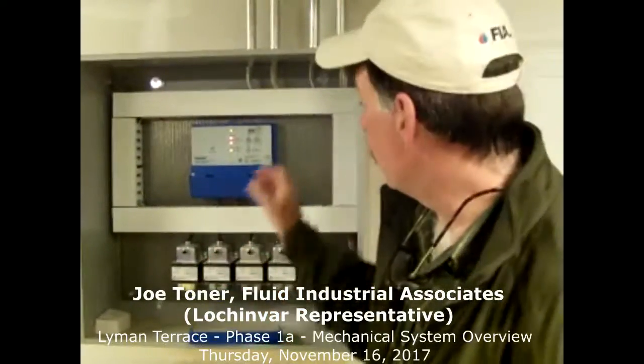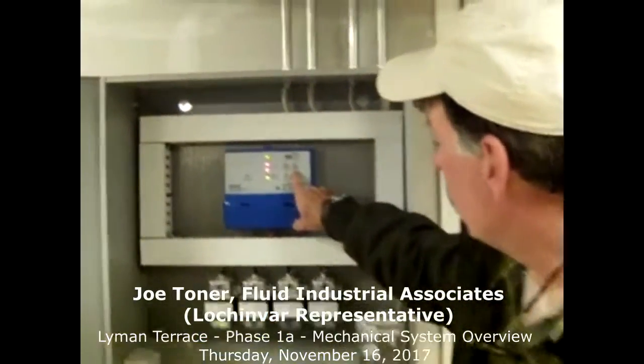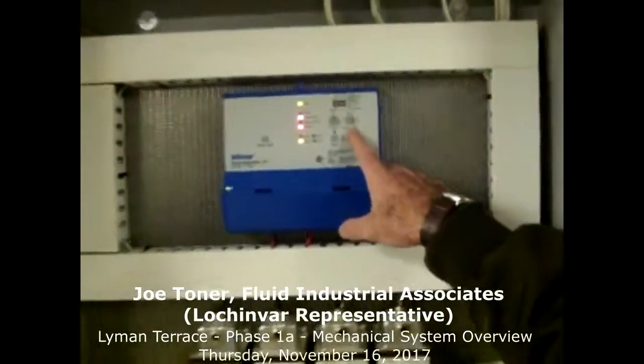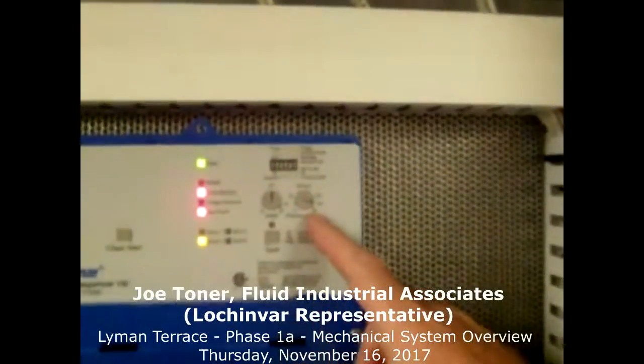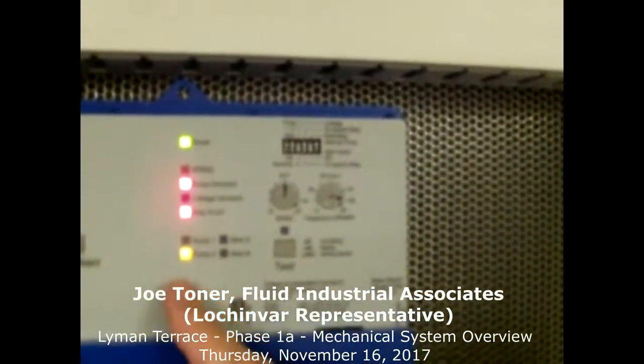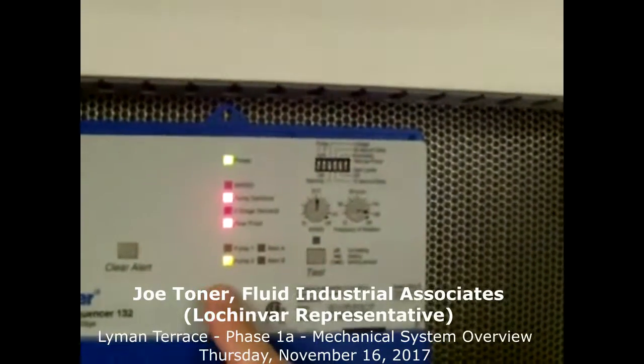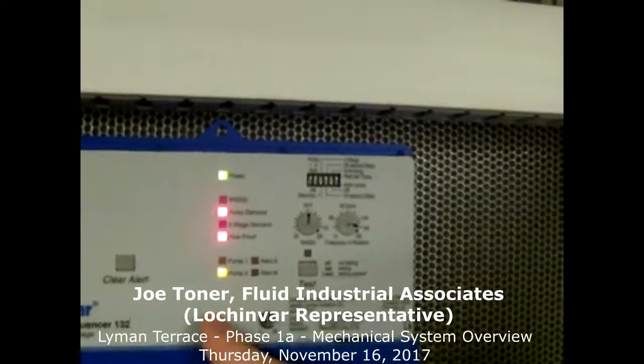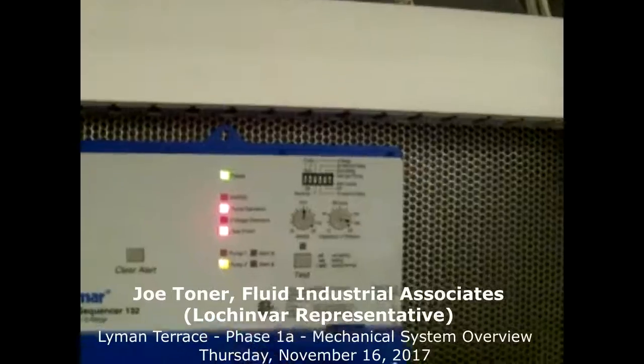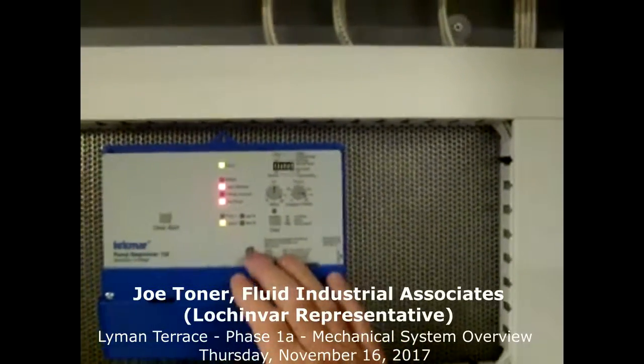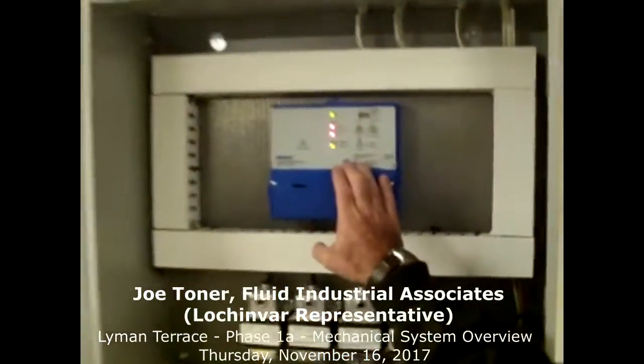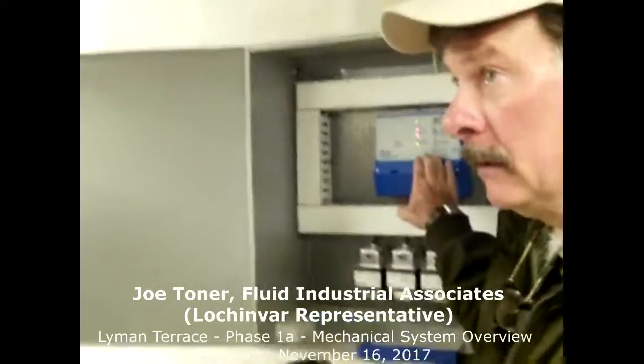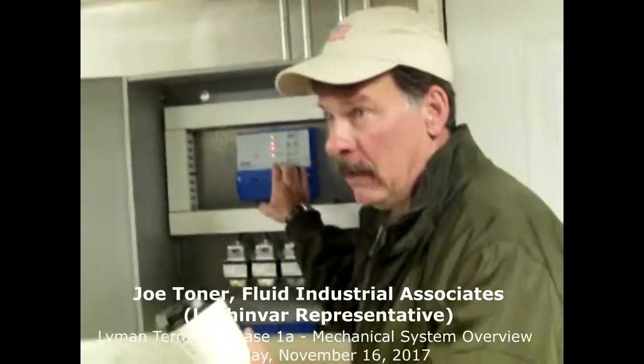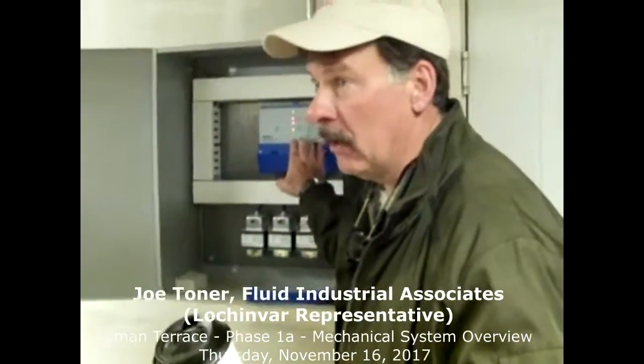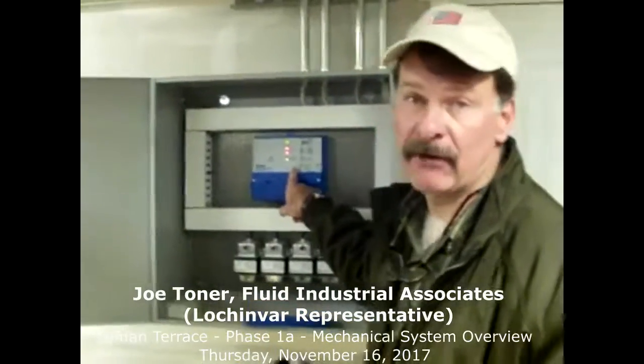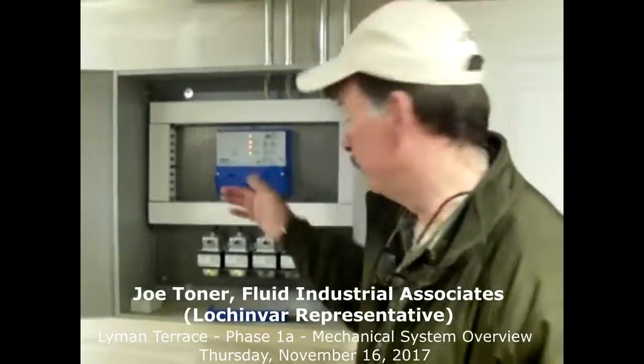The other thing it does is, and this has been dialed in for 168 hours of runtime, so after 168 hours of pump 2 running, it goes back to pump 1. And the idea there being equal runtime over time. So it's kind of a safety device, and again, this gets back to the physical inspection, because if you got a pump fail and it turns on the second pump and it runs, nobody knows about it unless you come down and see that you got some flashing lights and you got an issue going on.